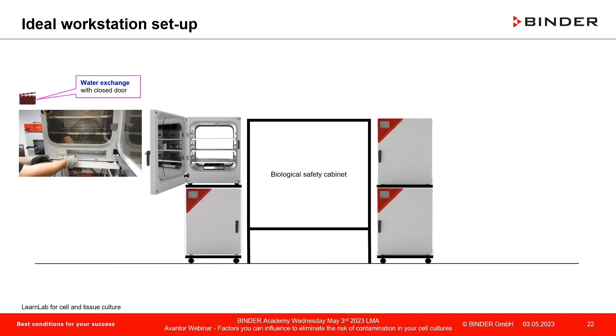If we revisit that clip, you can see we don't have to open the glass door, which means we're lowering - eliminating - the risk of contamination coming in from outside, and we're not disrupting the culture conditions. So CO2, temperature, and humidity stay very stable inside, in contrast to exchanging water with a water pan. That's also something you'd like to consider.